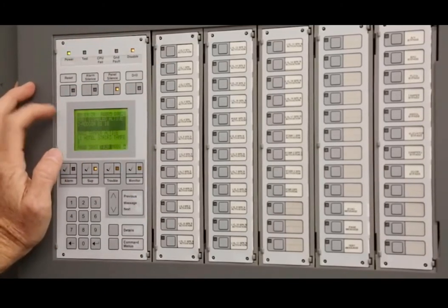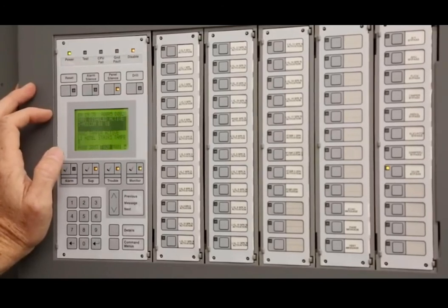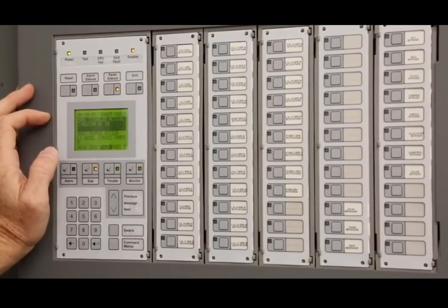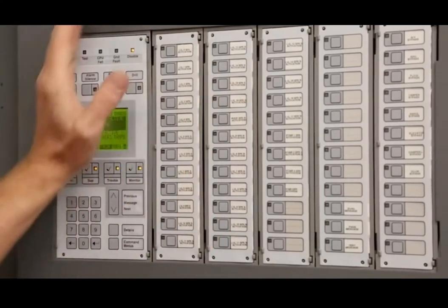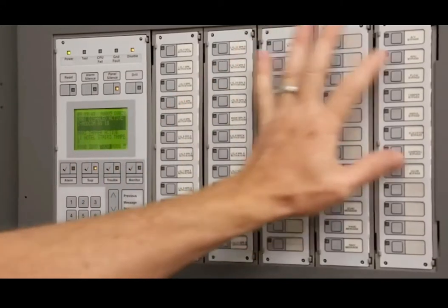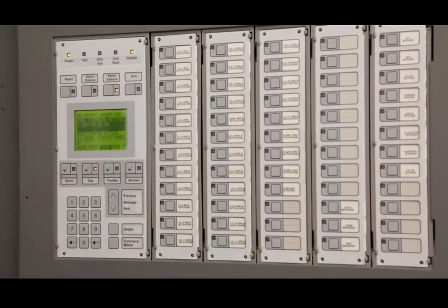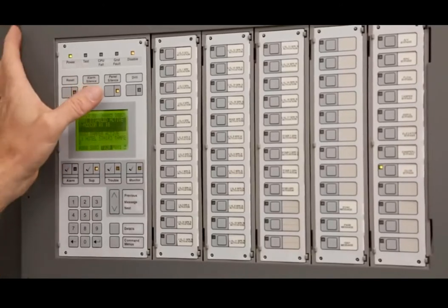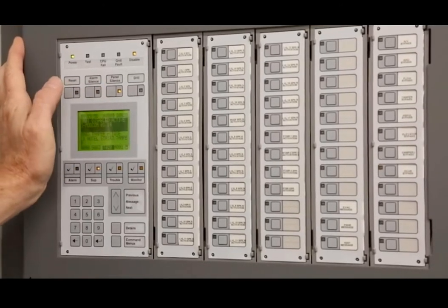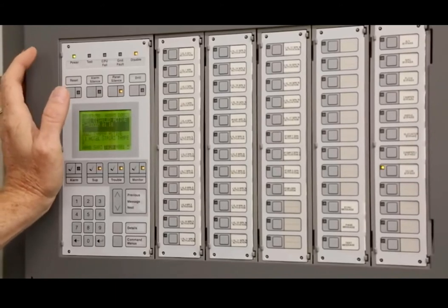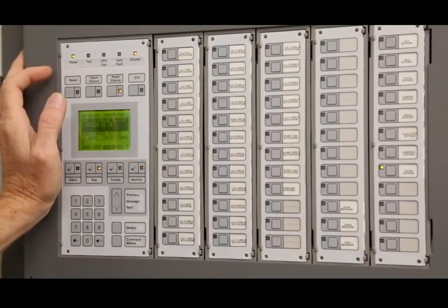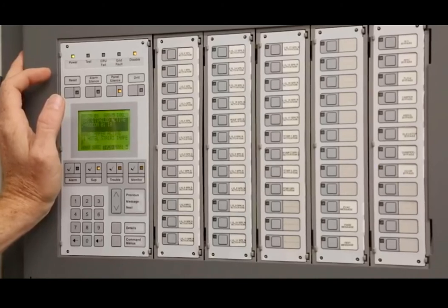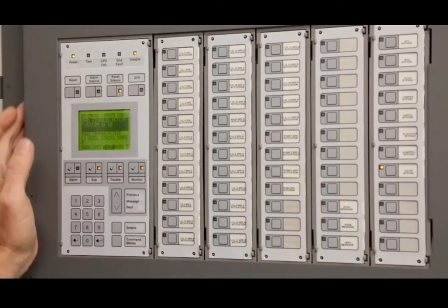This keyboard here is your main panel. We have a sub panel on the first floor North Electrical Room. They'll show the same display. Basically, just this portion right here will be shown over there. There are no bypass buttons or microphone over there, but you have commands over there just like I'm doing here. You can silence it, you can reset, and alarm silence from that location. Lobbies will have remote annunciators. Both lobbies will have one, and the security office will have one. So basically we have 5 locations where you could silence it or read the description.